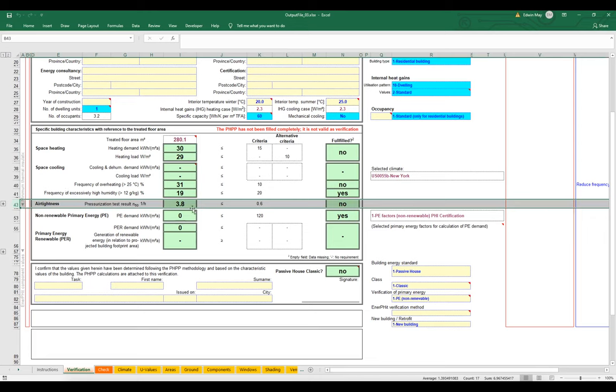We are currently inputting a value of 3.8 air changes per hour when tested at 50 Pascals of pressure. That's quite a bit higher than the reference target for new construction of 0.6, so we are not complying — we're supposed to be at 0.6 and we're currently at 3.8. Where did 3.8 come from? That's a very specific number. How did that get calculated?